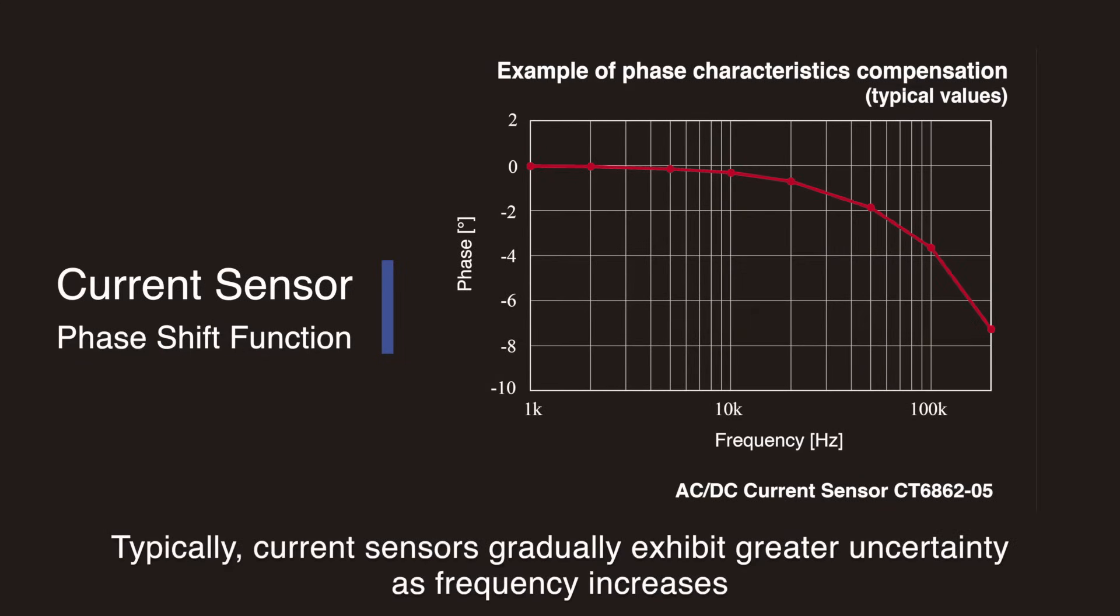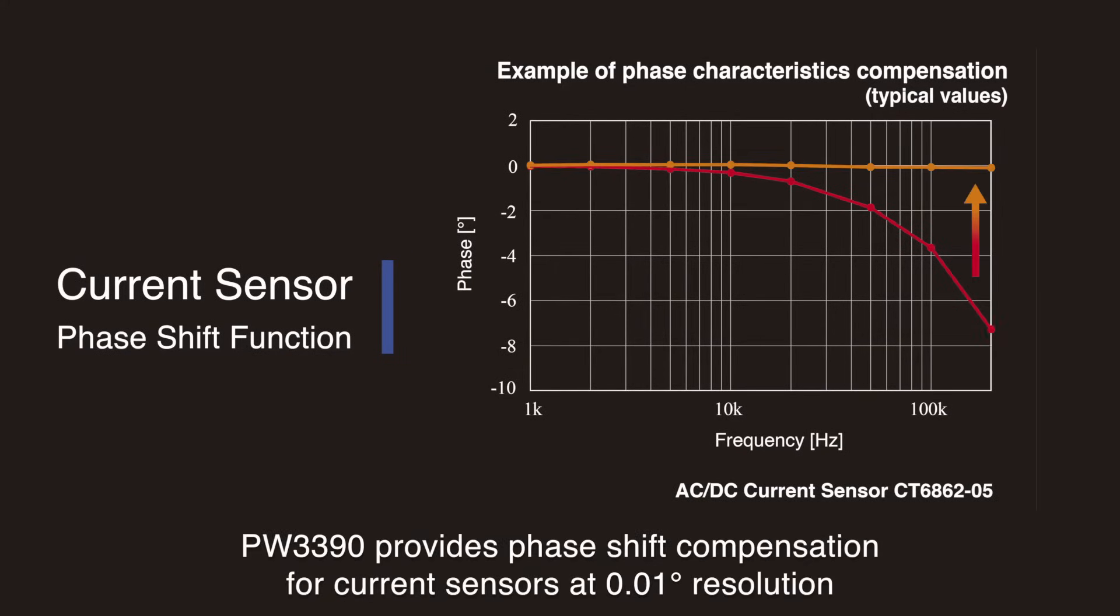In typical situations, current sensors will gradually exhibit greater uncertainty as the frequency increases. However, the PW3390 provides phase shift compensation for Hioki current sensors at a 0.01 degree resolution.